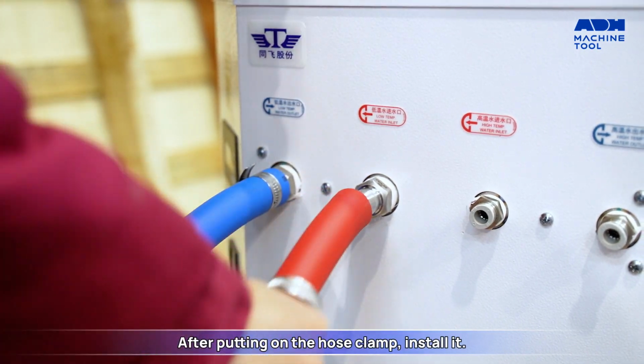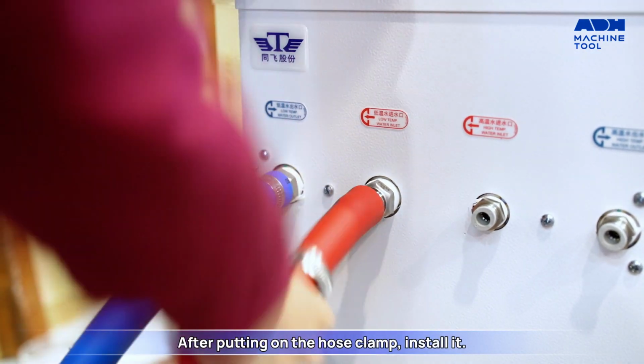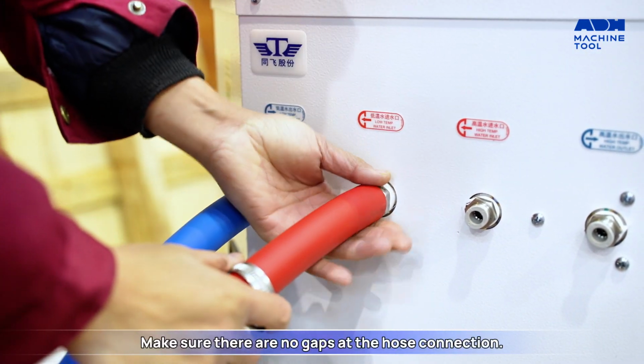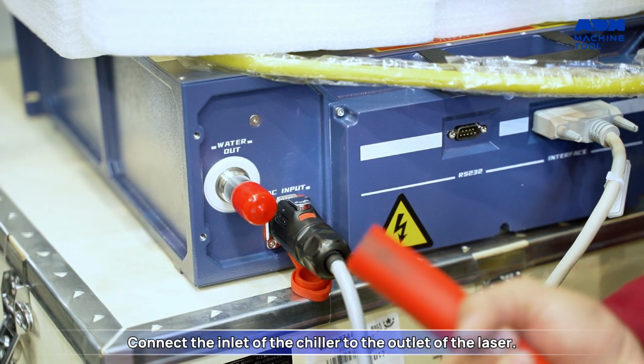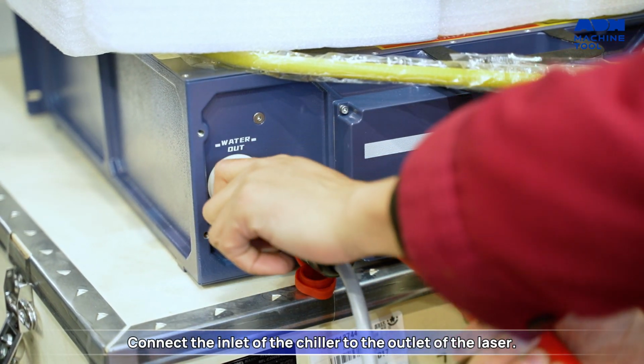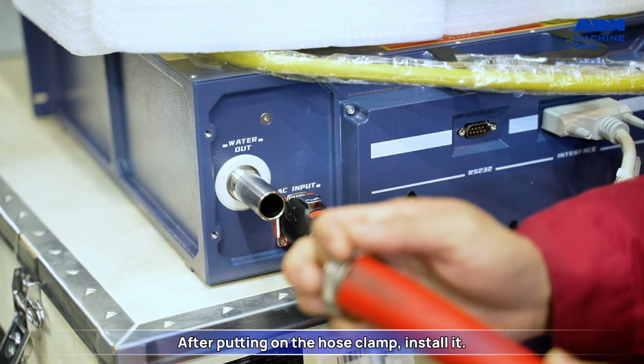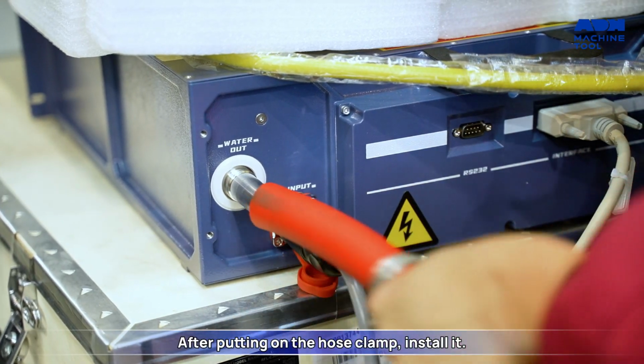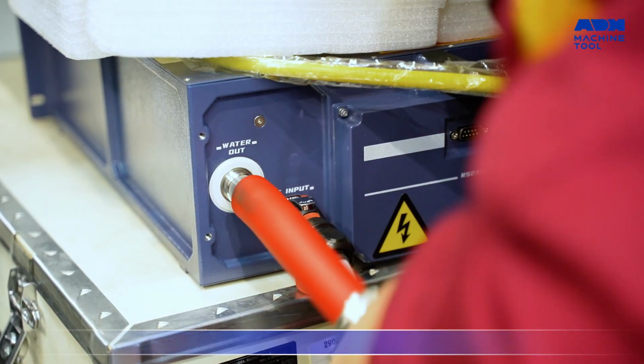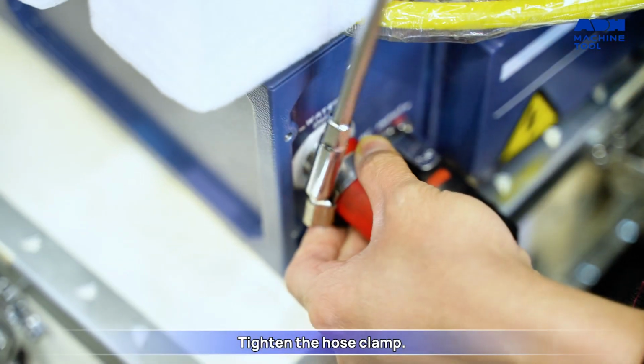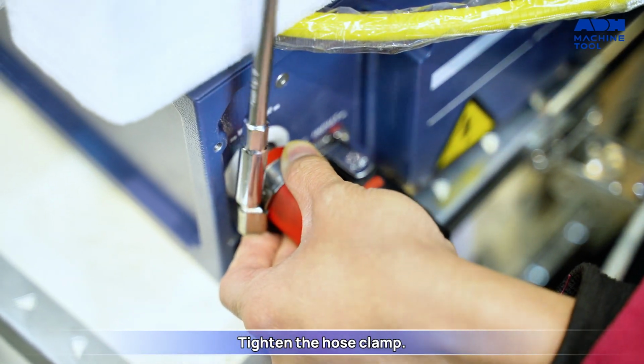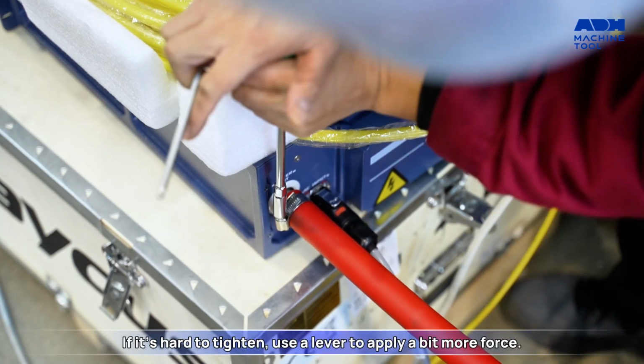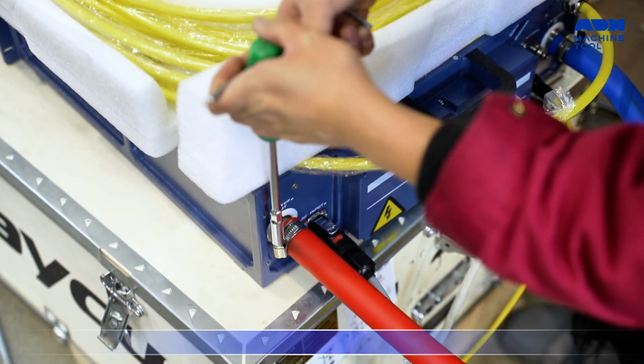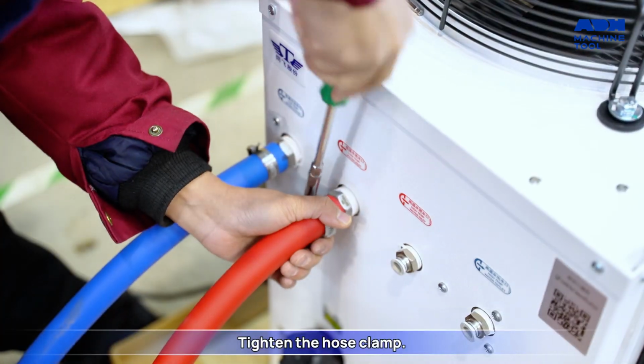After putting on the hose clamp, install it. Make sure there are no gaps at the hose connection. Connect the inlet of the chiller to the outlet of the laser. After putting on the hose clamp, install it. Tighten the hose clamp. If it's hard to tighten, use a lever to apply a bit more force. Tighten the hose clamp.